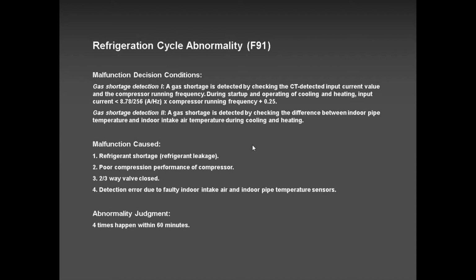But if it's the compressor, then it's a long process. So thankfully, our compressors are in good shape. I hardly get bad compressors. Also, I hardly get bad PCBs. Most of the time, my calls would be low refrigerant, low on gas. There's a leak somewhere here and there. And once in a while, obviously, I'll get a bad electronic expansion valve, fully corroded, mostly in ocean areas.